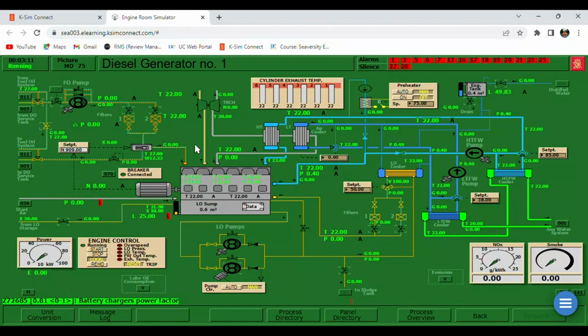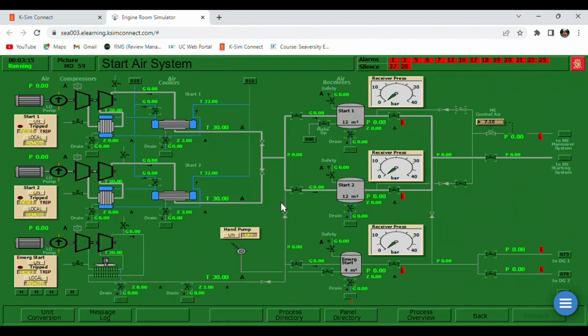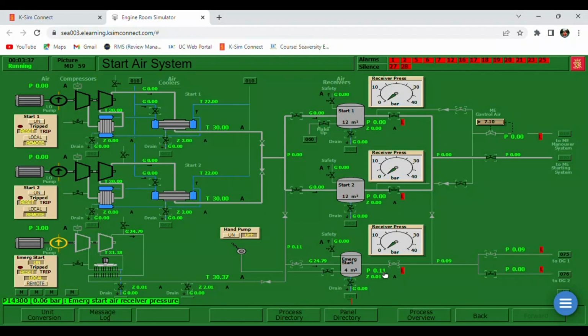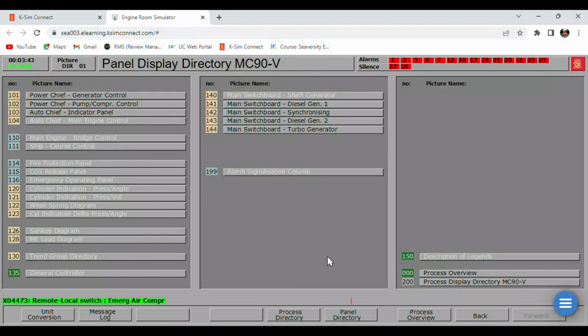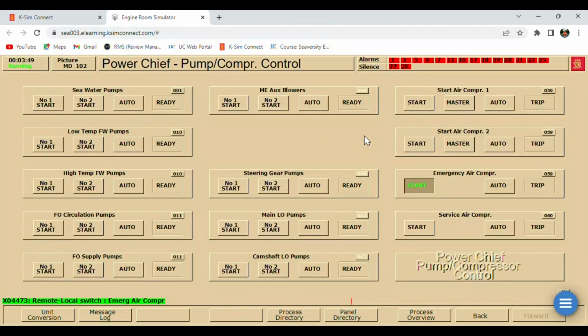So now I'm going to proceed to diesel generator number 1 and set it up. First I'll go to the starting air and make sure that we have air over here. I'm going to open these valves and we can start this emergency compressor. Put it local and put it on. Our pressure here should increase, and once done, you can put it in remote and put it on automatic. So go here in the panel directory, go here in the auto control.